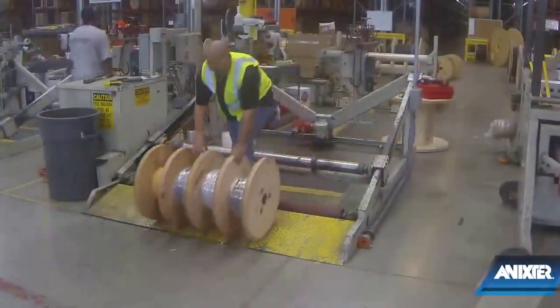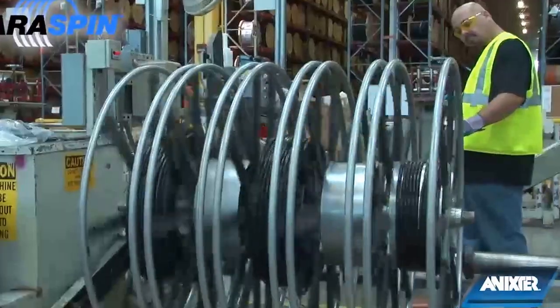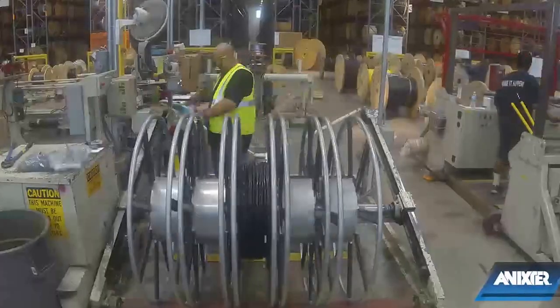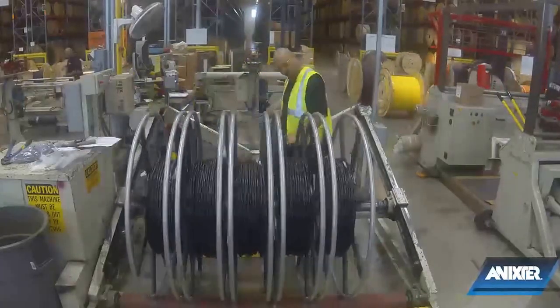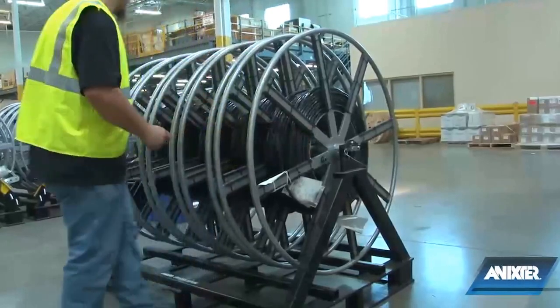The ground wires can also be layered on their own standard reel. When using Anixter's ParaSpin reels, layering can be done with the phase conductors and the grounds, as each chamber spins independently, which allows each conductor to pull at its own rate. ParaSpins also ship on their own caddy, which eliminates the need and labor for setting up jack stands.